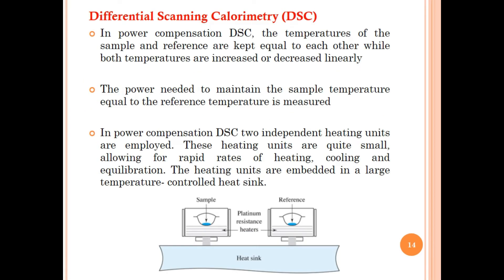In power compensated DSC, the temperatures of the sample and reference are kept equal to each other while both temperatures are increased or decreased linearly. The power needed to maintain the sample temperature equal to the reference temperature is measured. Two independent heating units are employed; these heating units are quite small, allowing for rapid rates of heating, cooling, and equilibration. The heating units are embedded in a large temperature-control heat sink.